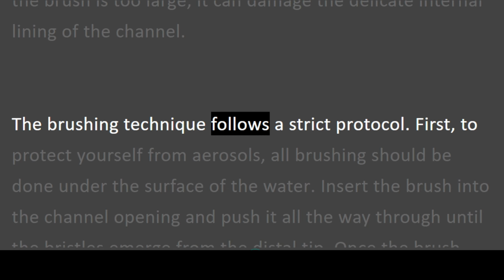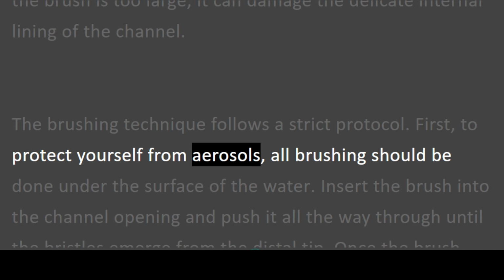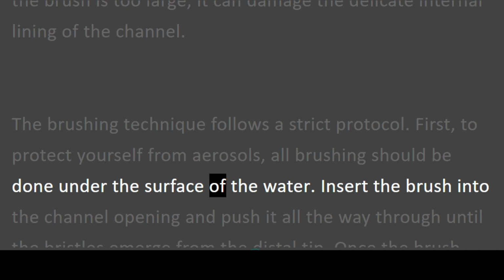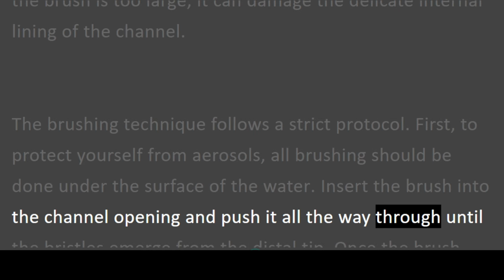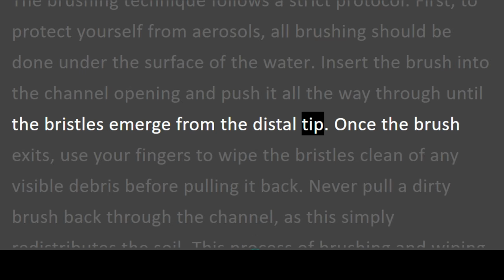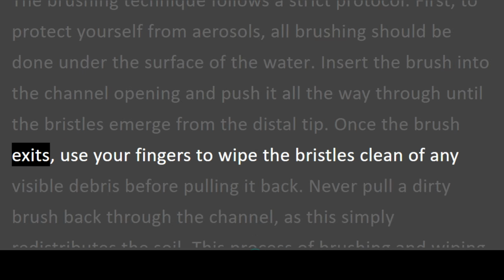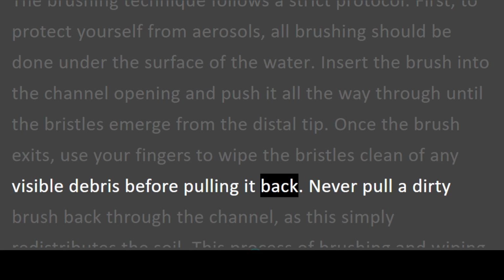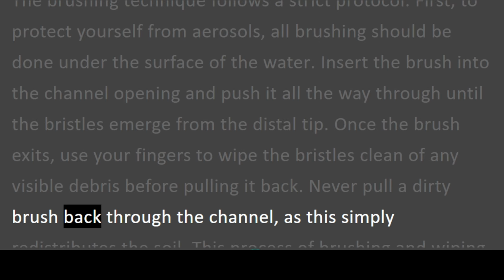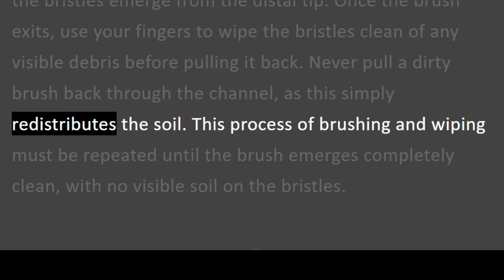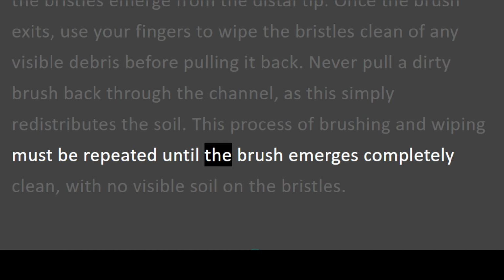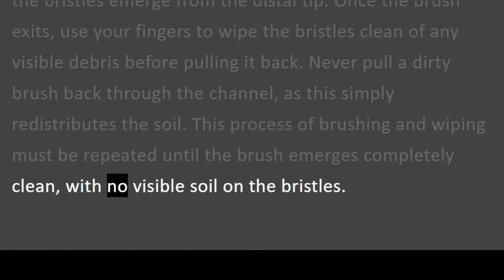The brushing technique follows a strict protocol. First, to protect yourself from aerosols, all brushing should be done under the surface of the water. Insert the brush into the channel opening and push it all the way through until the bristles emerge from the distal tip. Once the brush exits, use your fingers to wipe the bristles clean of any visible debris before pulling it back. Never pull a dirty brush back through the channel, as this simply redistributes the soil.